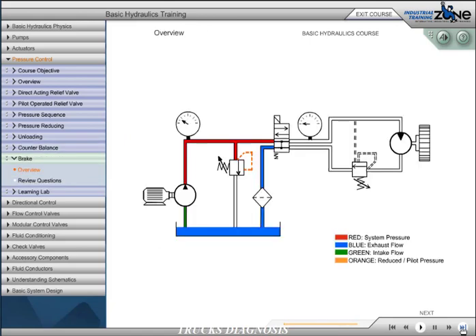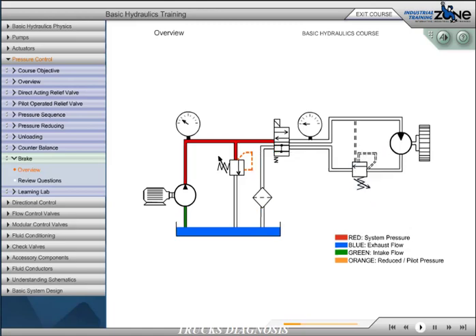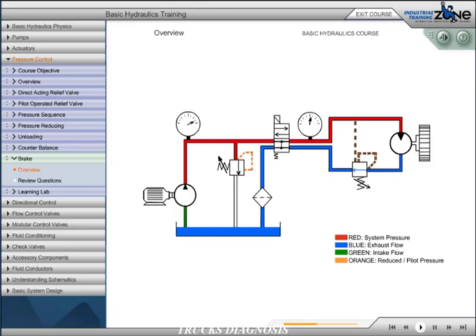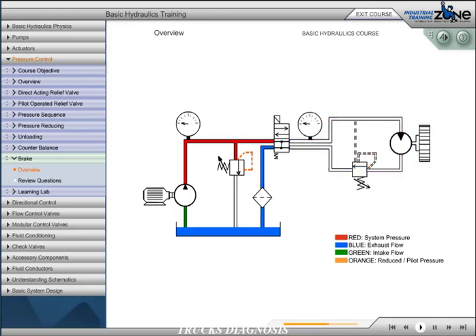A brake valve is a normally closed pressure control valve with both direct and remote pilots connected simultaneously for its operation. This valve is frequently used with hydraulic motors for dynamic braking. Because any downstream resistance will add to the load on the hydraulic motor, we pilot remotely using working pressure to keep the valve open during running. This eliminates back pressure on the motor. When we de-energize the directional valve, remote pilot pressure is lost, allowing the valve to close. The inertia of the load will now drive the valve open via the internal pilot, giving us dynamic braking.